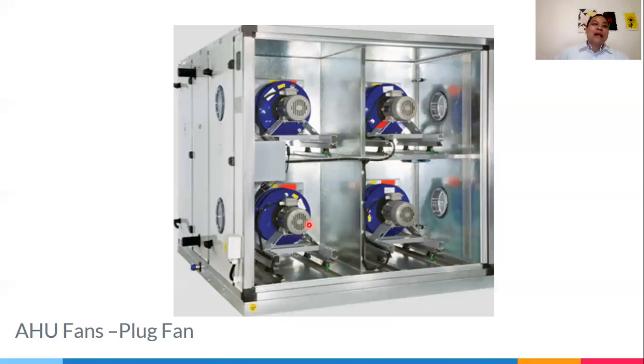Usually it's part load capacity, commonly around 80%, sometimes as high as 90%, or 75%, generally between 70 to 80% is our usual load. At that load, three plug fans will be more efficient, consuming less electricity than one big centrifugal fan. So that's the advantage of using the plug fan.